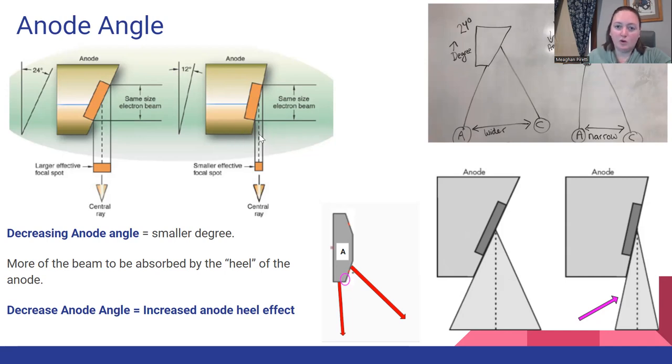This is going to cause more loss of intensity on the anode side than the other one. An increase in anode angle, bigger anode angle, less heel in the way. So decrease anode angle, smaller, increase your anode heel effect.